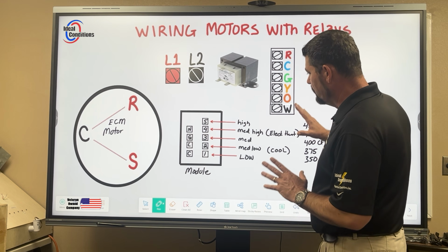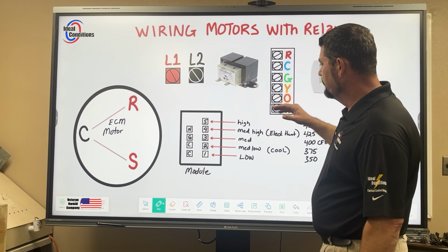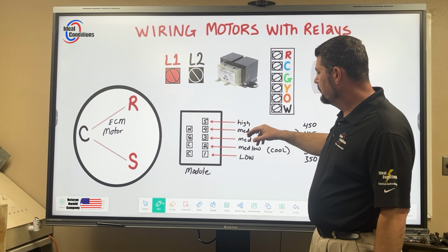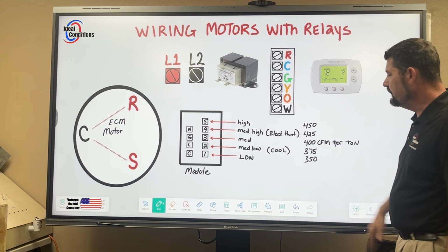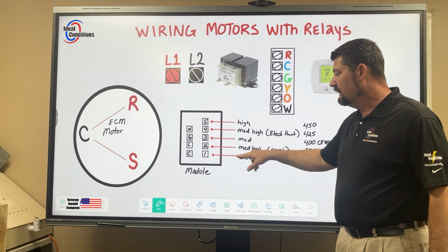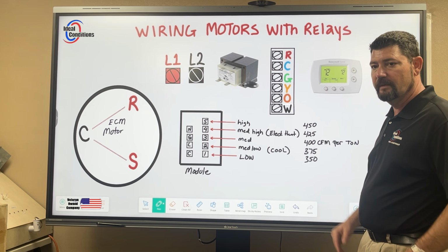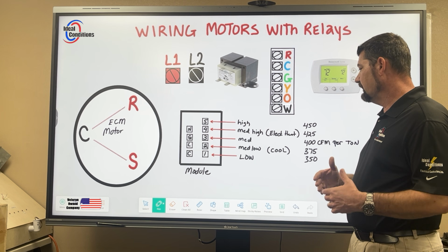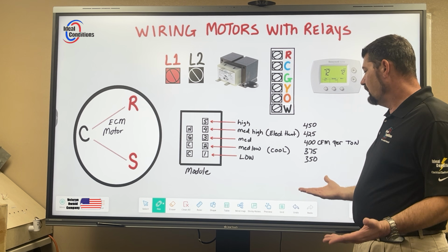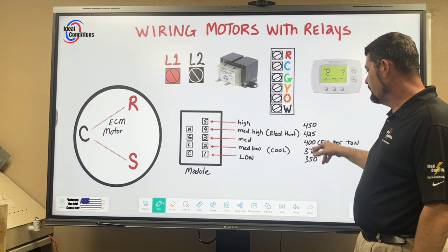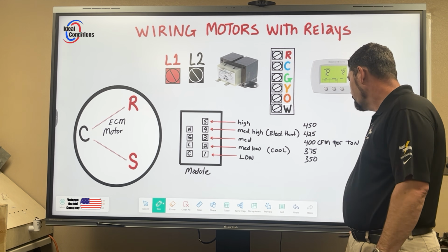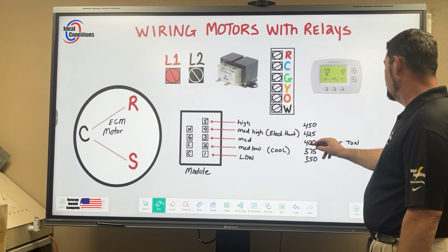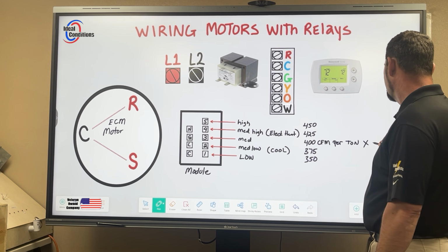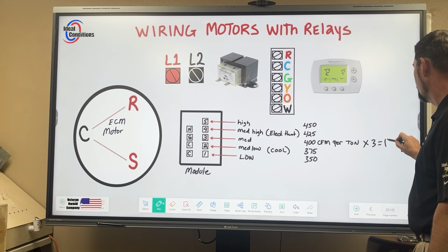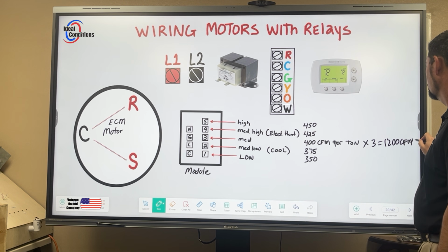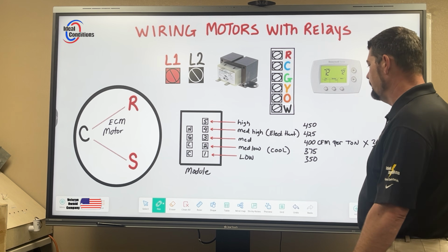I've labeled some of this, so I'm going to go ahead and just show you here those speed taps 1 through 5. Here are the speeds and here are the CFMs. We have 1 is low speed. That's 350 CFMs per ton. And so for example, if we had a 3 ton, we would multiply any one of these 3-digit numbers by 3. So we can do a couple here. We can say if I have medium speed times 3 equals 1200 CFMs, right? And so that's typically what we base everything off of anyways.